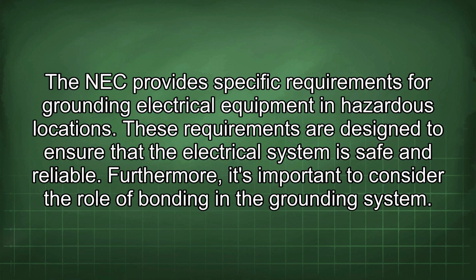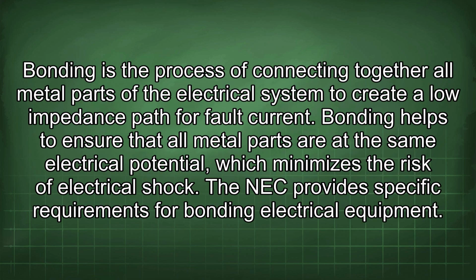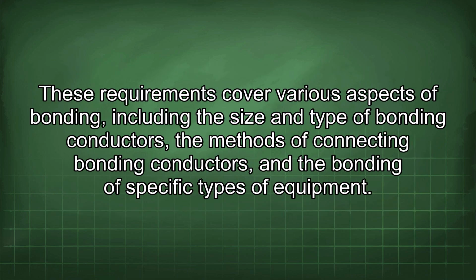Furthermore, it's important to consider the role of bonding in the grounding system. Bonding is the process of connecting together all metal parts of the electrical system to create a low impedance path for fault current. Bonding helps to ensure that all metal parts are at the same electrical potential, which minimizes the risk of electrical shock. The NEC provides specific requirements for bonding electrical equipment. These requirements cover various aspects of bonding, including the size and type of bonding conductors, the methods of connecting bonding conductors, and the bonding of specific types of equipment.